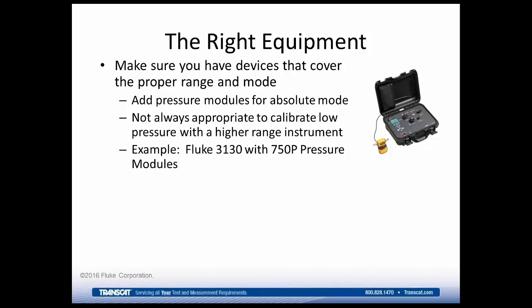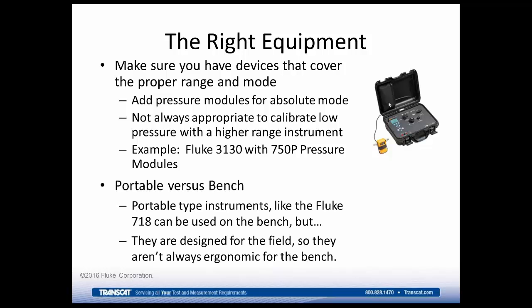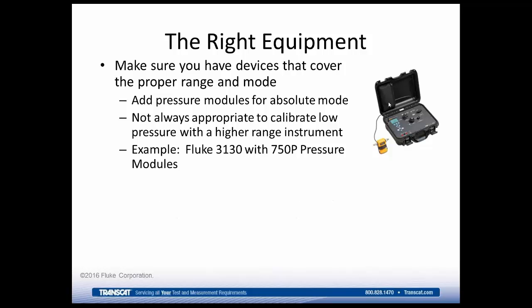But once again, that's something you can possibly get around by adding pressure modules or similar. An example here is the Fluke 3130 that we show here with a 750P pressure module. The 3130 has an internal range of 300 psi gauge. If I wanted to calibrate absolute mode devices, I can simply connect an absolute mode 750P module, or if I want to calibrate very low ranges like a draft range, or high pressures, I could possibly do the same by adding those range 750P modules as well.